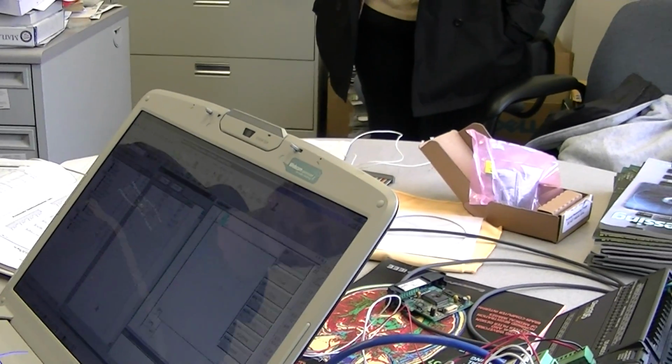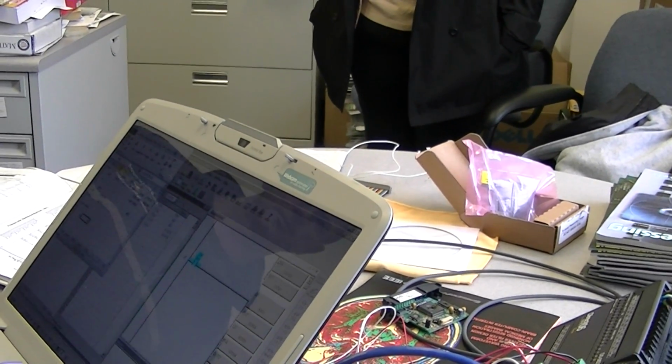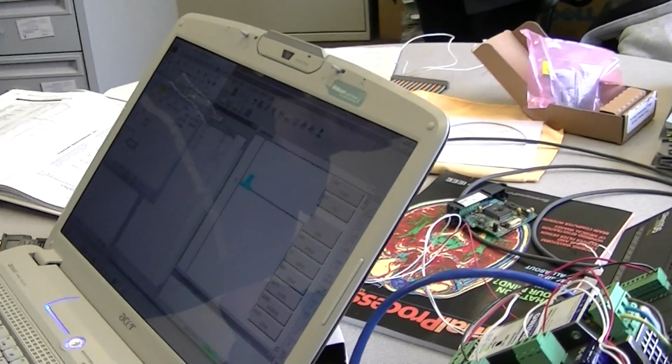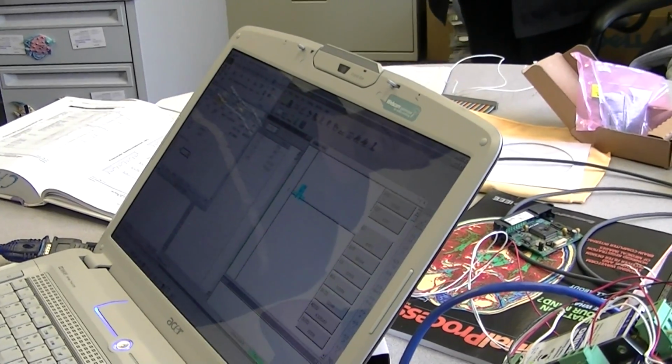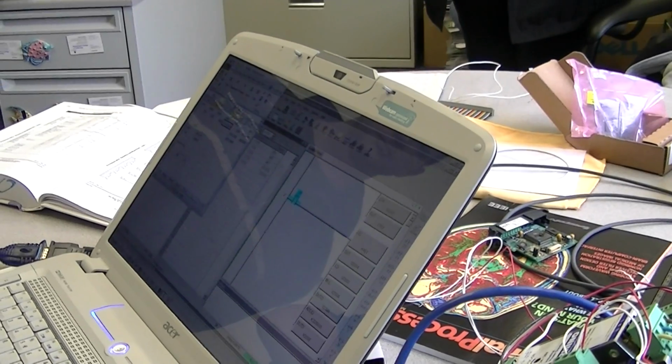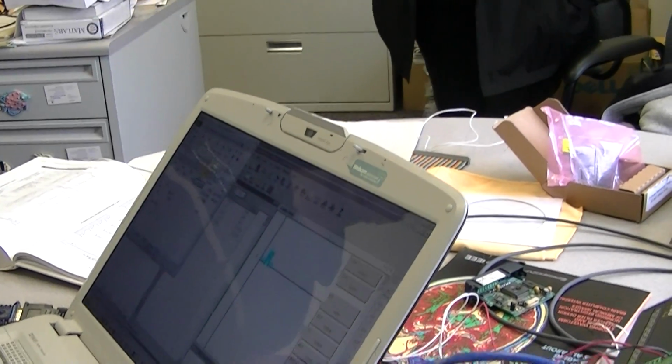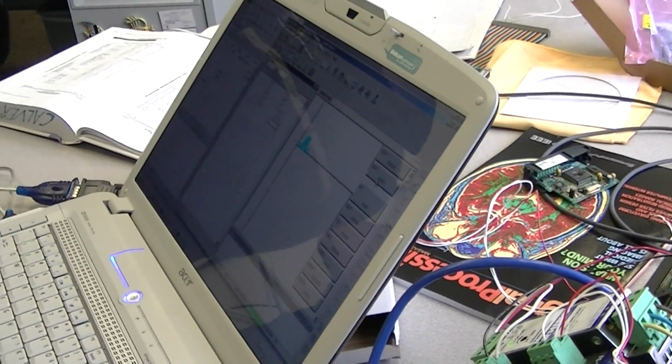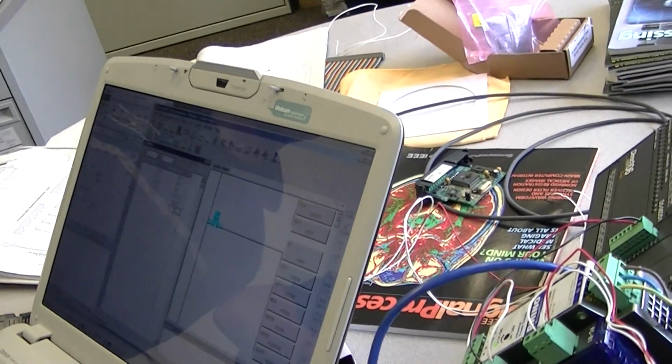But I go back to my spreadsheet again, and up here I know what the minimum temperature the thermocouple or the RTD can read. I know what the maximum is. I know how many ticks. I do some mathematical formulas and compute a calculation, if you will. And basically I can go through all this, this is a series of calculations on a PLC. And it claims, unfortunately, that the temperature is 74.2.